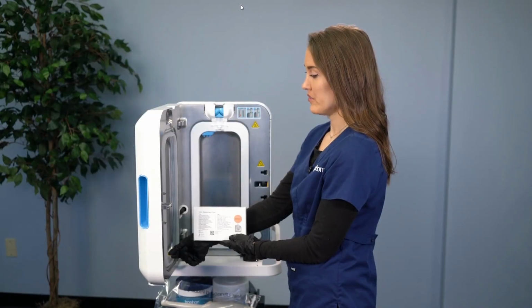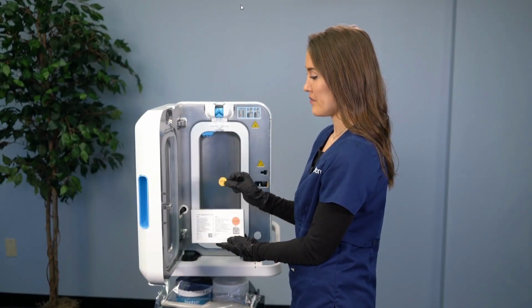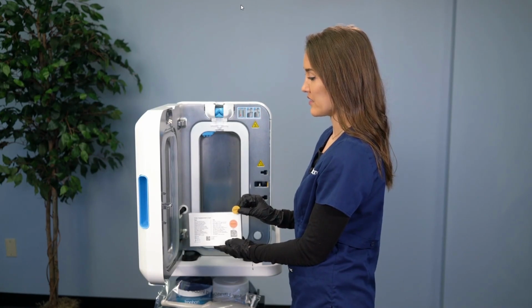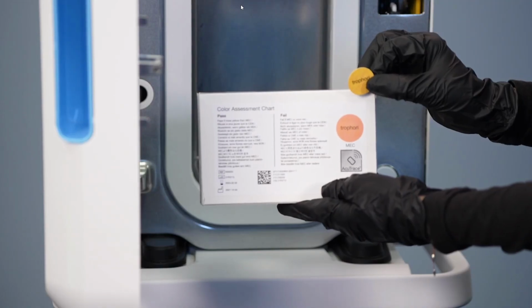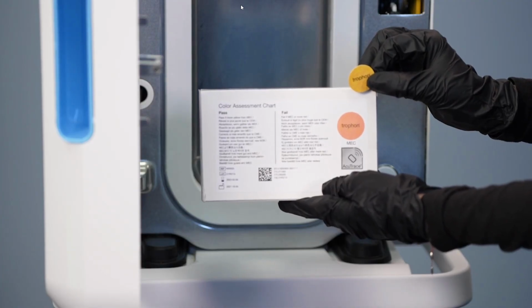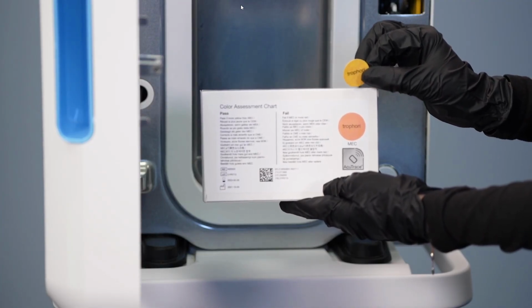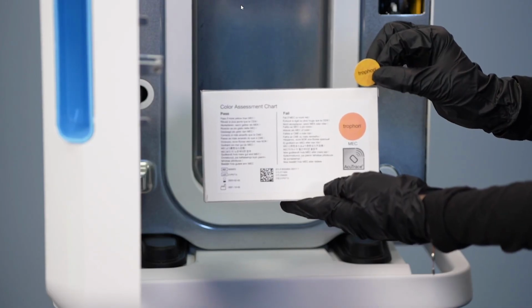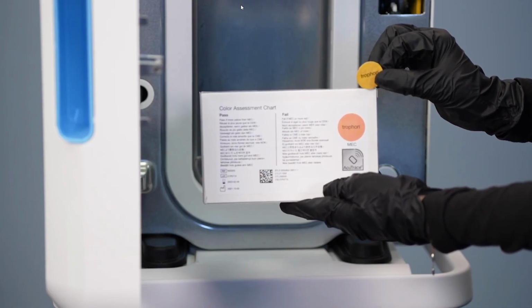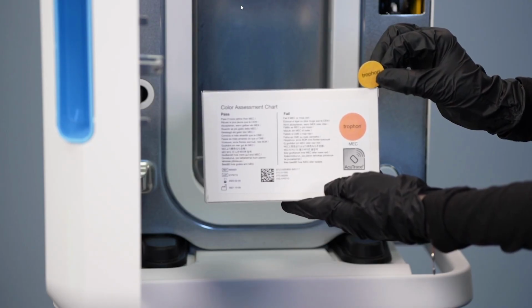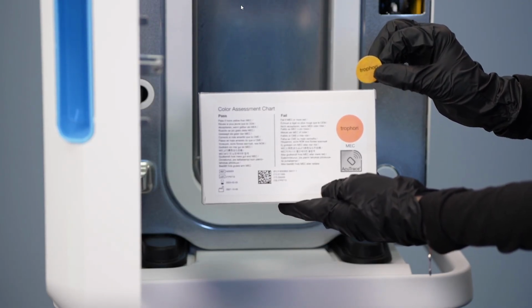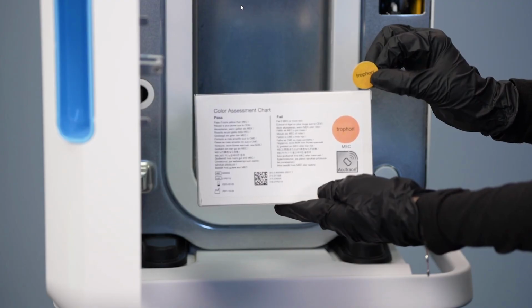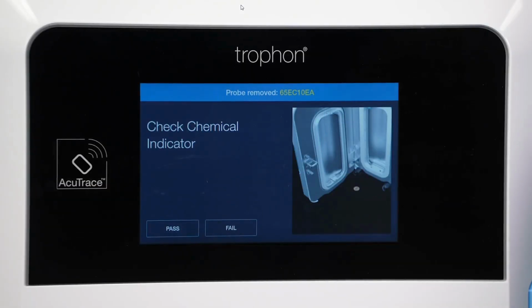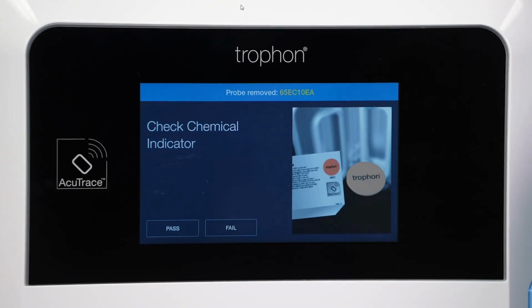Now remove the chemical indicator and validate by comparing it to the minimum effective concentration, or MEC, on the box it was removed from. Note that the color is lighter or more yellow than the MEC, indicating a successful disinfection cycle. If your indicator or your touch screen indicate a cycle fail, you will rerun a cycle using a new chemical indicator.